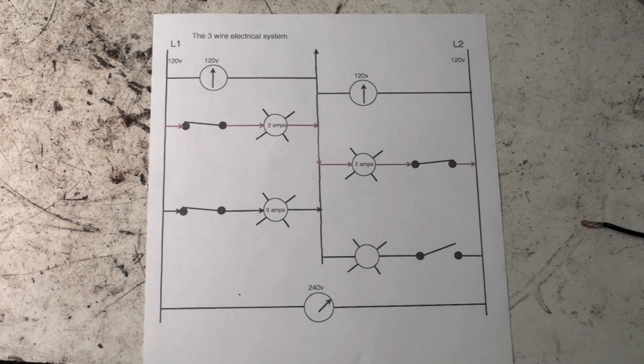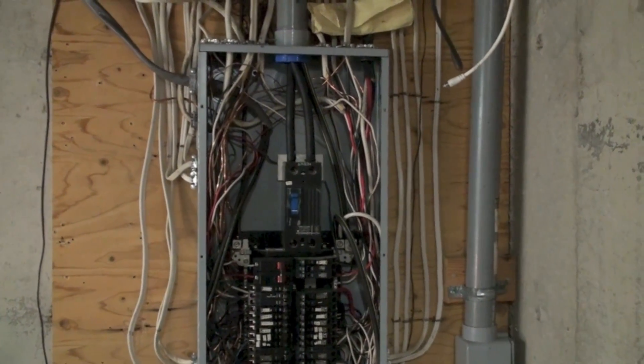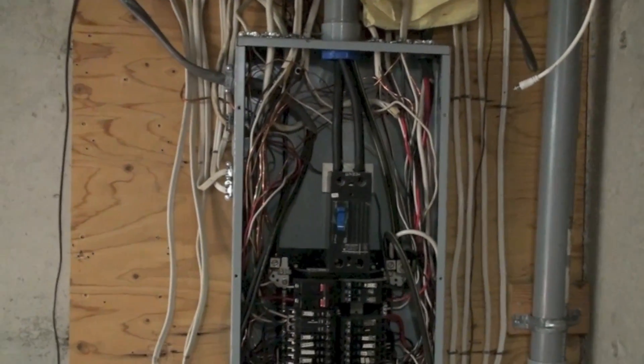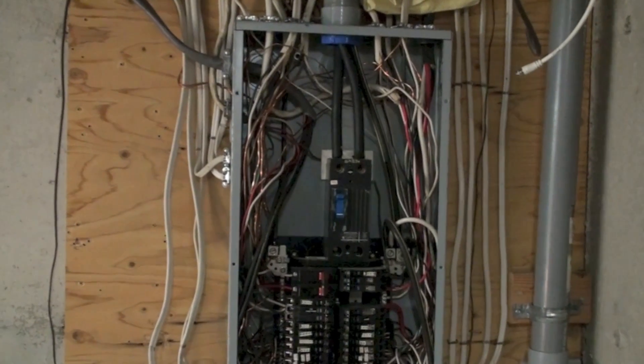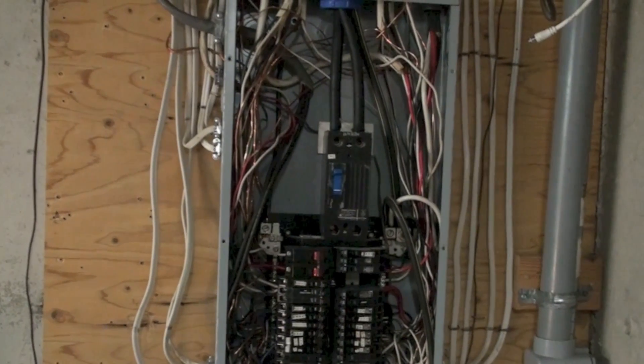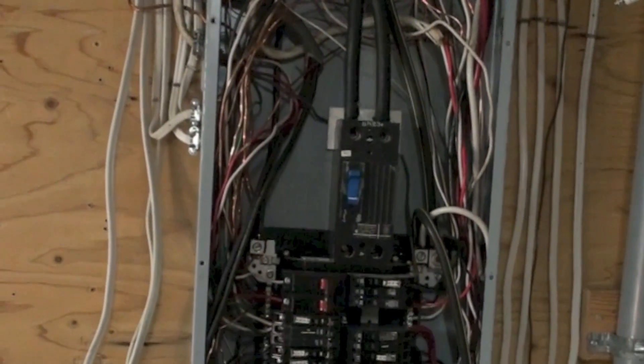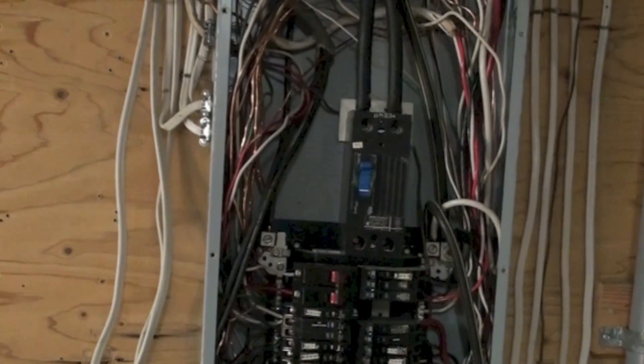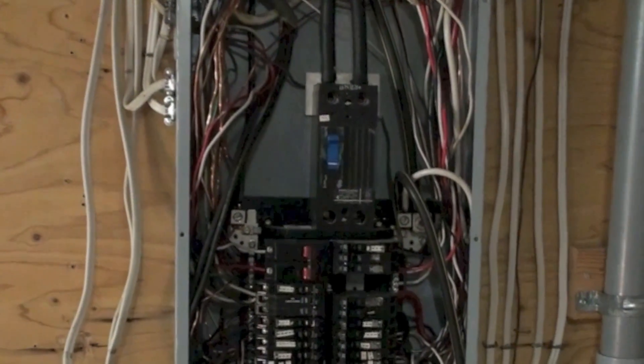I'm going to show you what this looks like in a panel. It's a little harder to tell what's going on there, but I'll try to point it out. Here we're showing a panel, and you can see the main breaker right there in the center and the two big black wires going to it—that's my L1 and my L2. To the right of that, you'll see the neutral wire. The neutral wire is going down to the terminals right there, just below the breaker. That is the neutral side. Those are the only three wires that are coming into this panel.